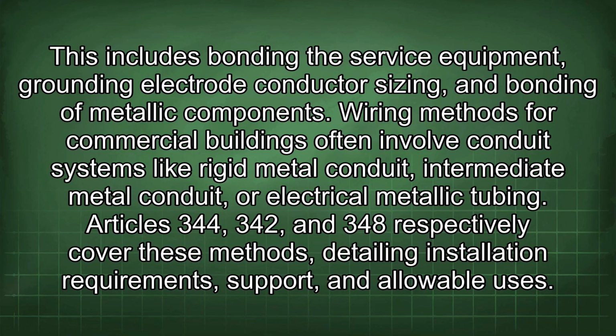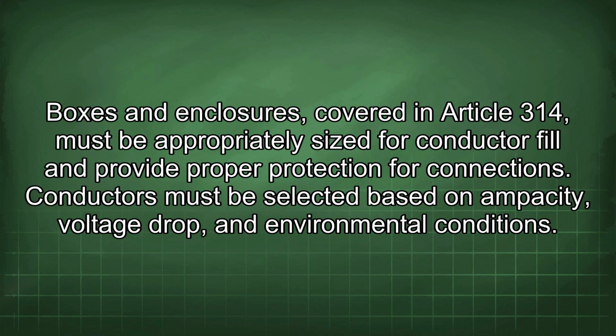Wiring methods for commercial buildings often involve conduit systems like rigid metal conduit, intermediate metal conduit, or electrical metallic tubing. Articles 344, 342, and 348 respectively cover these methods, detailing installation requirements, support, and allowable uses. Boxes and enclosures, covered in Article 314, must be appropriately sized for conductor fill and provide proper protection for connections.